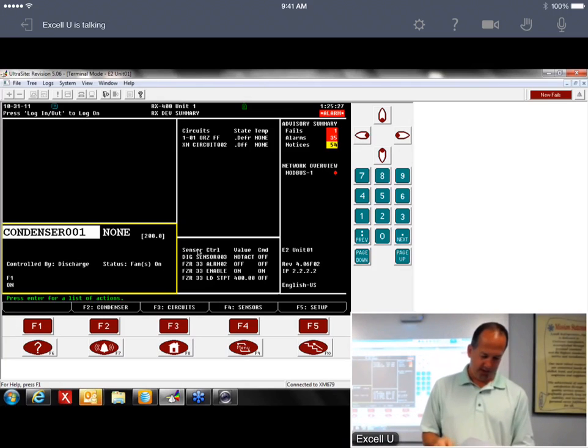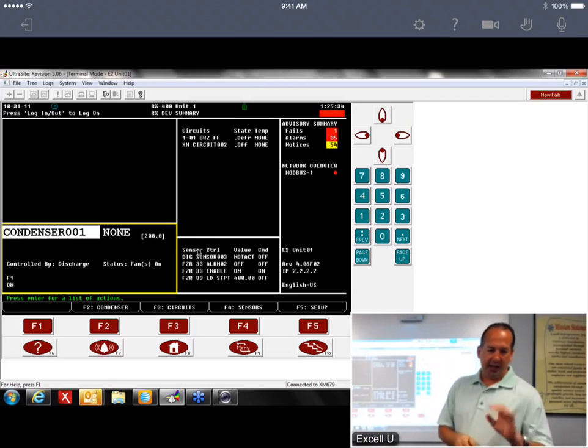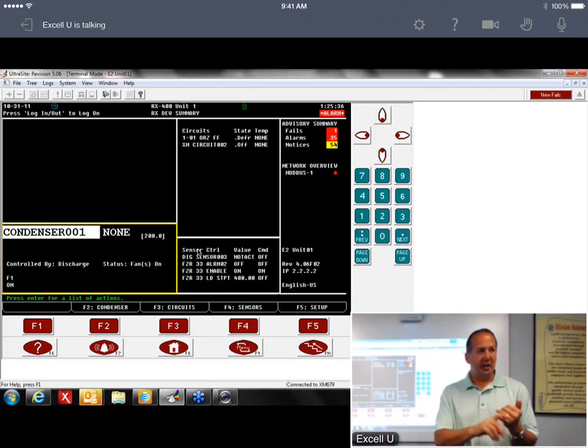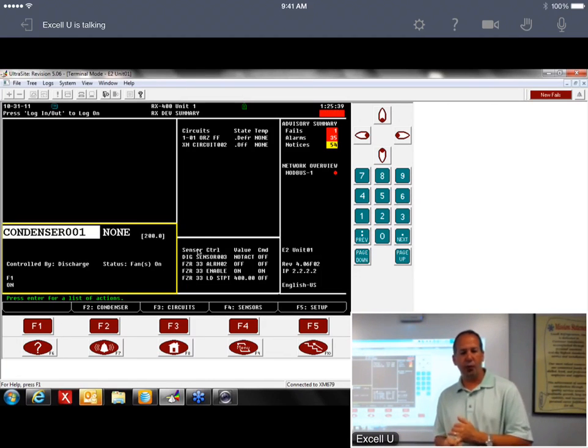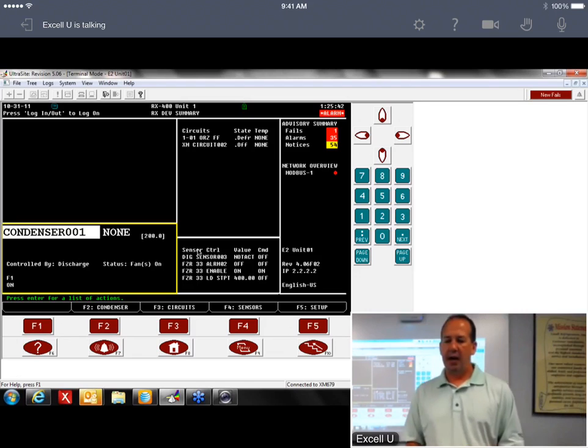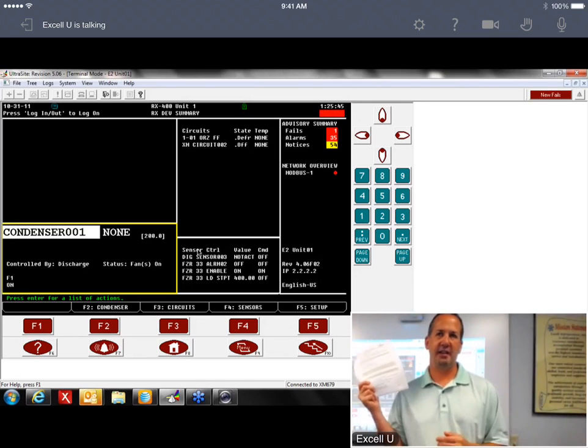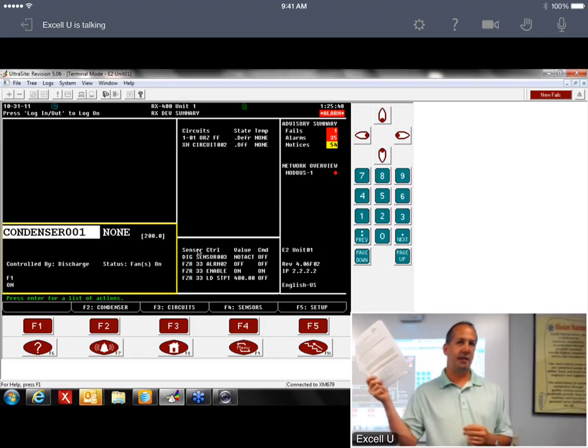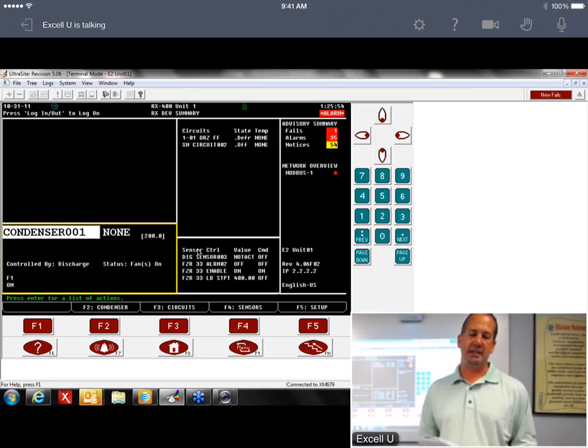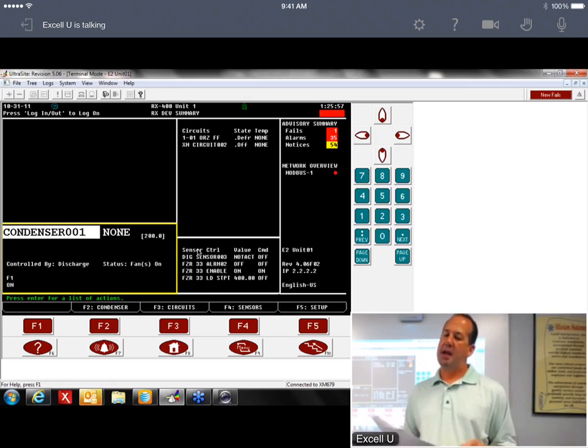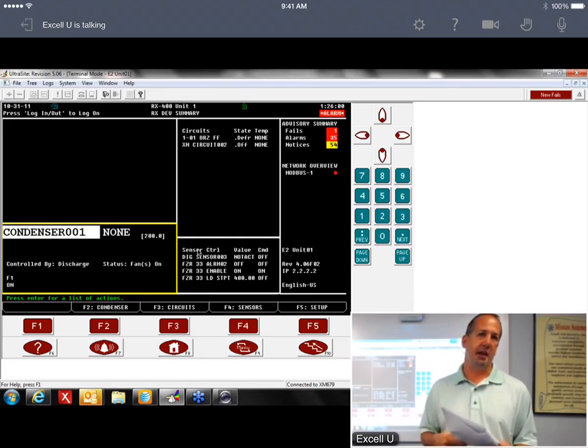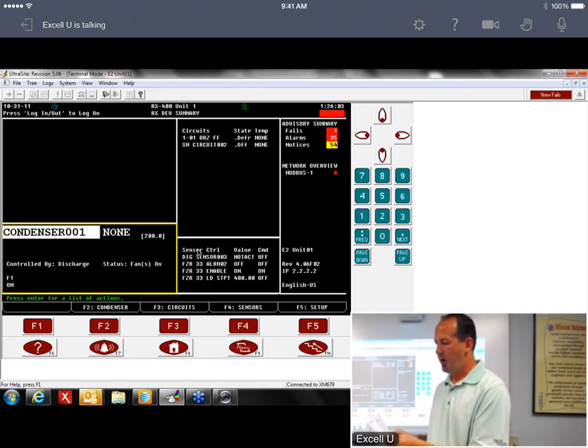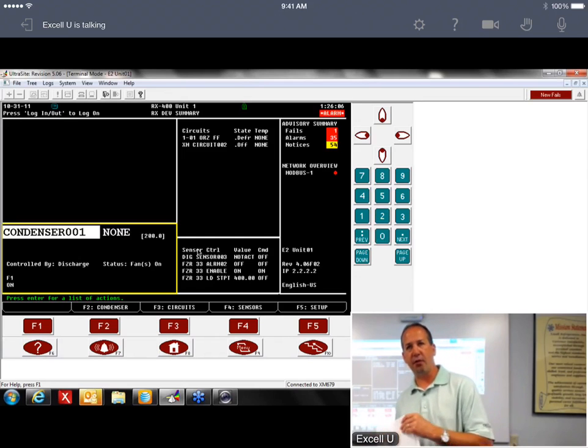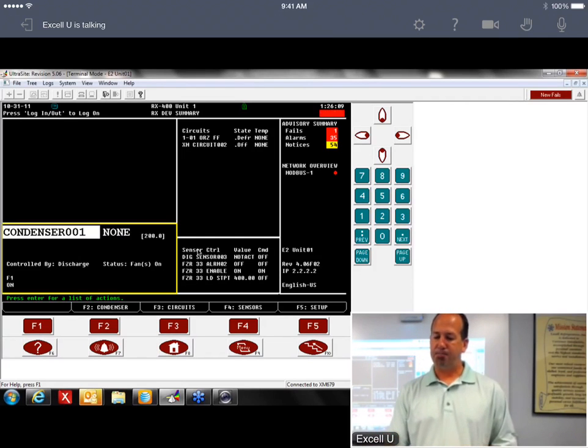We hit the Modbus. Okay, so again, I would program the E2 when you get a new rack from Hill Phoenix on a new store — it's going to have it in there. I'd still go through this checklist and make sure. Hill Phoenix has got this and they're supposed to be programming per this, but that doesn't always happen. If I were you guys, when you get a new rack that's already got the program in it, I'd go through and double check to make sure they hit everything. This sheet just walks you through the steps of setting up the device, the circuit, and associating them.